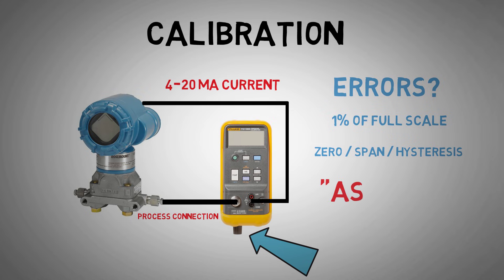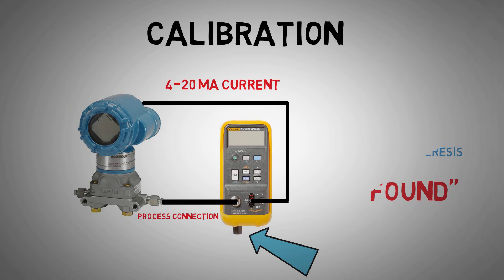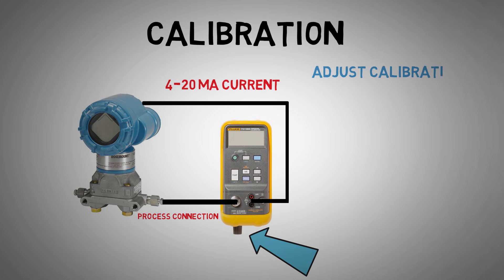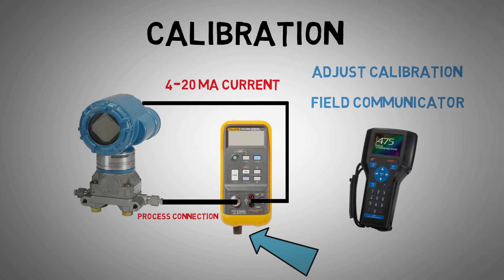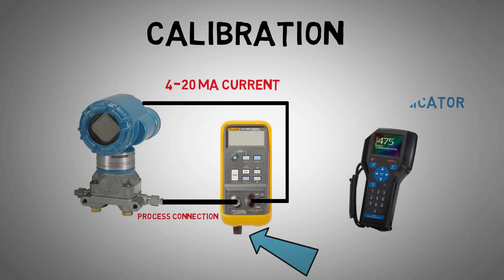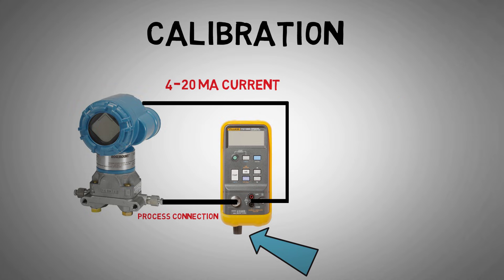This is called the as-found test. If the pressure transmitter is out of its calibration limits, we would adjust the range or zero, either through local potentiometers or buttons on the transmitter, or more commonly on newer equipment, digitally via a field device communicator such as a HART communicator. We would then repeat the test to ensure we have met our calibration standard. This is called the as-left test.